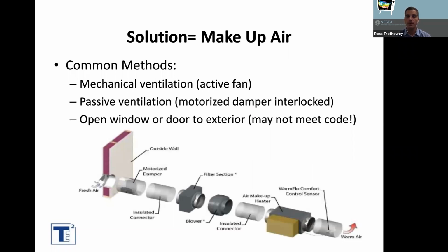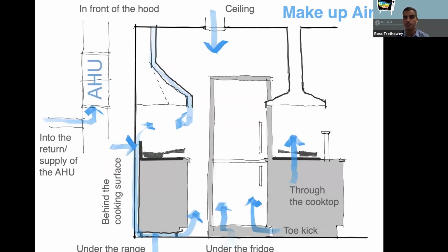So how do we deal with makeup air? Typically, you see three different methods being used. One is mechanical ventilation, with an active fan that brings in the outside air. Another option is passive ventilation, which is typically done by a motorized damper, which is interlocked. And the third option is a fixed louver or just an open window or open door concept, which may not meet code, obviously. I've just grabbed a diagram from one of the manufacturers showing one way it's done in cold climates. Fresh air is brought in through a motorized damper, through an insulated connector, because this could condense, filtered, put through a fan, put through a heater, and delivered back to the space. That's a common way that it's done as well.